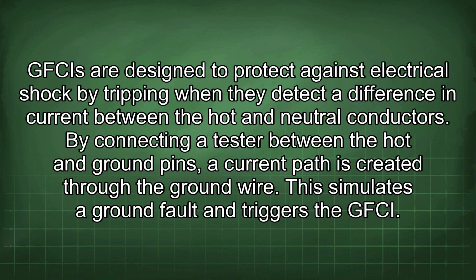GFCIs are designed to protect against electrical shock by tripping when they detect a difference in current between the hot and neutral conductors. By connecting a tester between the hot and ground pins, a current path is created through the ground wire. This simulates a ground fault and triggers the GFCI.